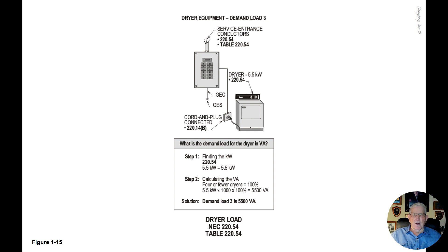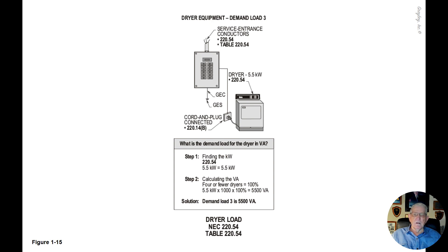This illustration deals with dryer loads in accordance with NEC 220.54 and Table 220.54. We're figuring the VA by applying a demand load for the service entrance conductors as well as for a feeder — not a branch circuit. We have one dryer, so with four or fewer dryers we take them at 100%. One dryer at 5.5 kW; also review cord-and-plug connection per 220.14(b) and grounding per 250.140.